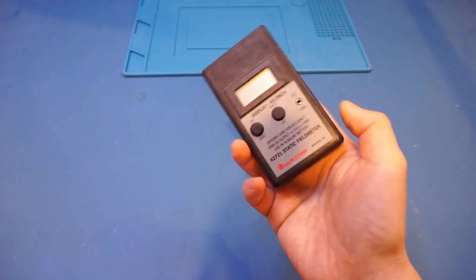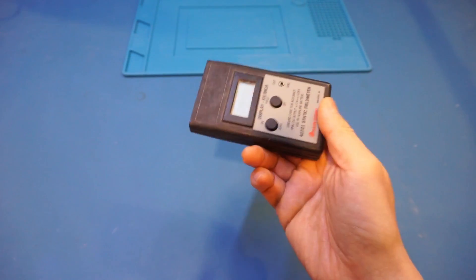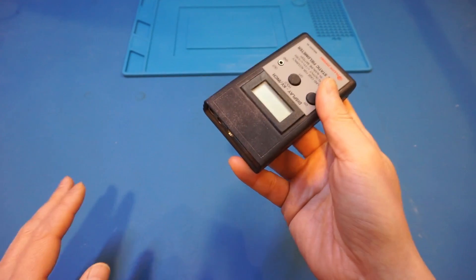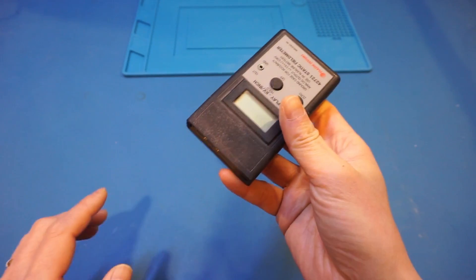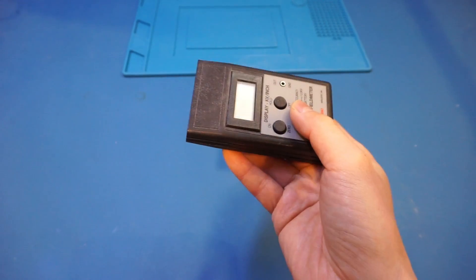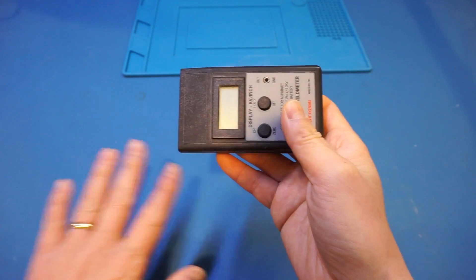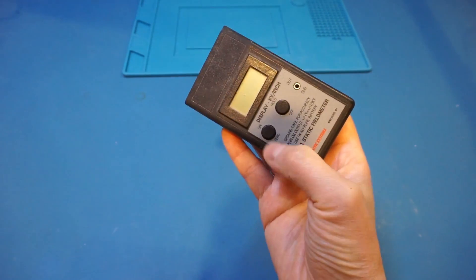We can verify the effectiveness of my ESD mat with this static field meter. Now, I'm actually just going to use an ESD mat to calibrate the meter. Technically speaking, I should use a known ground potential surface to do that, but in this case, we're mainly interested in the relative readings, so it doesn't really matter, although I know the ESD mat is grounded at ground potential. So let me actually turn it on here.